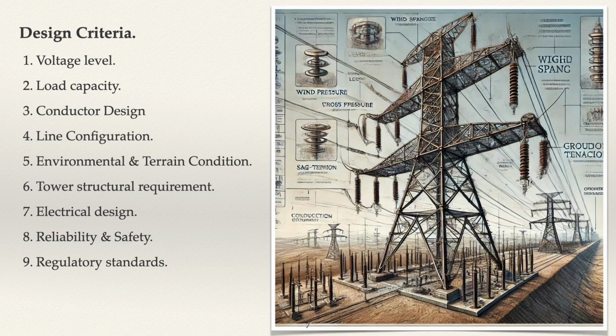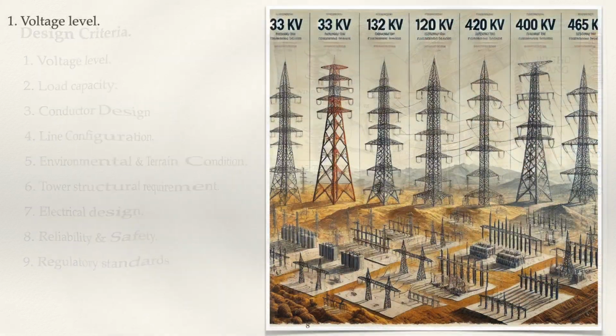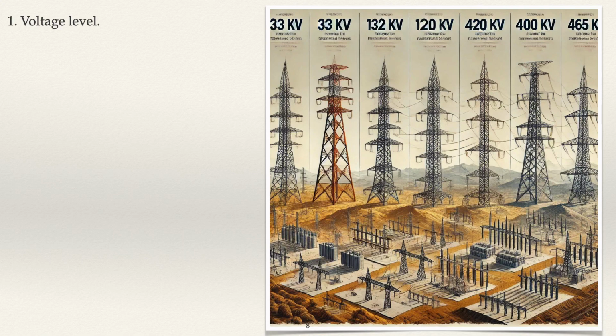and approval. Design parameters required are as mentioned. 1. Voltage level. 2. Load capacity. 3. Conductor design. 4. Line configuration. 5. Environmental and terrain condition. 6. Tower structural requirement, 7. Electrical design. 8. Reliability and safety. 9. Regulatory standards. Let us understand each topic of design criteria in brief.